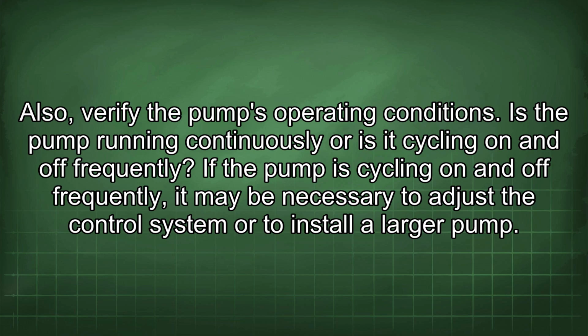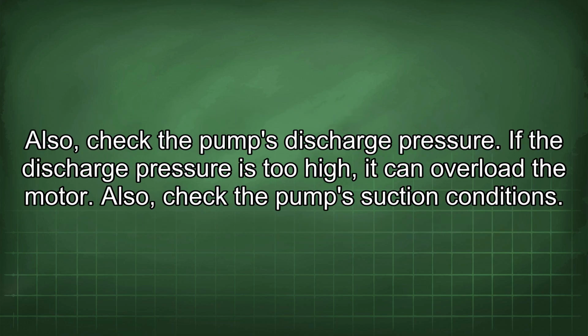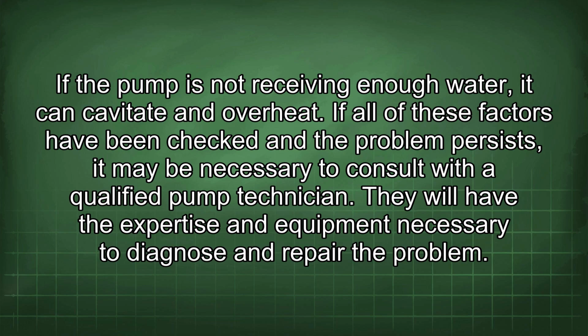If the pump is cycling on and off frequently, it may be necessary to adjust the control system or to install a larger pump. Also, check the pump's discharge pressure. If the discharge pressure is too high, it can overload the motor. Also, check the pump's suction conditions. If the pump is not receiving enough water, it can cavitate and overheat.